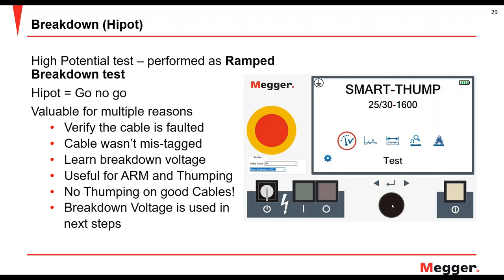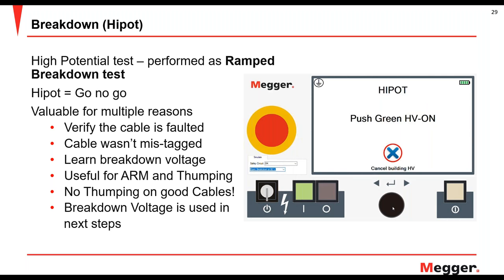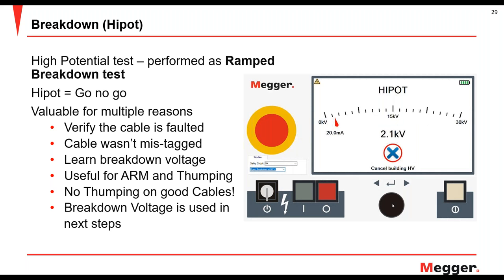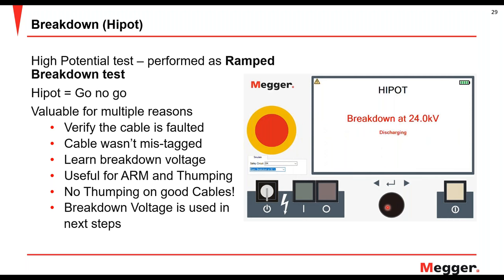Here is a simulation of the high pot function. We're going to high pot a 35 kV cable, going up to about 30 kV — the highest this unit can go. We're going to stress the cable and see where it flashes over. As you can see, it's slowly ramping up. You can see where it actually flashes over. It's either going to hold all the way to 30 kV — in which case it holds for five seconds and tells you no flashover occurred — but as you can tell here, it flashed over at 24 kV, letting you know that's our number for this particular cable and instance. You might reshoot it and it might vary: it might go up to 25 or 26, or it might be as low as 16. So every time, you want to start with high pot and then proceed, so you know what voltage to use for your arc reflection and thumping.